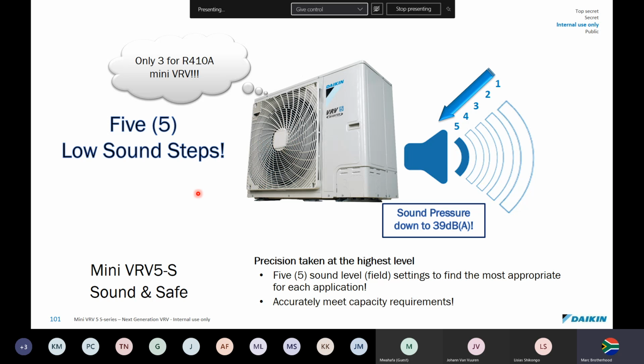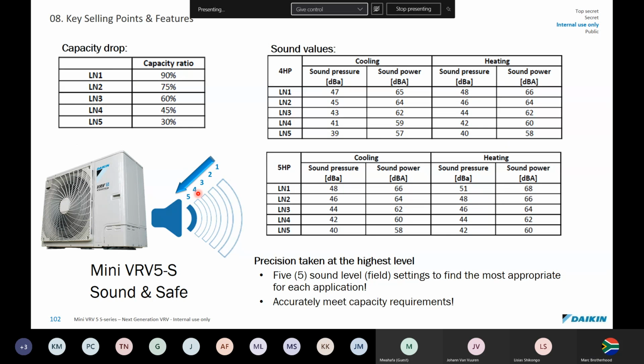So we limit the fan speed, we alter the head pressure control, and we have to monitor head pressure control and condensing temperature, which will all have effect on the saturated temperature going into your evaporator. So these are all fancy decibel ratings, which we're not too worried about, but you can see here the capacity ratio. When we go to a low noise level 5, the unit's only working at 30% of its capacity. So that's not ideal on a very hot night.